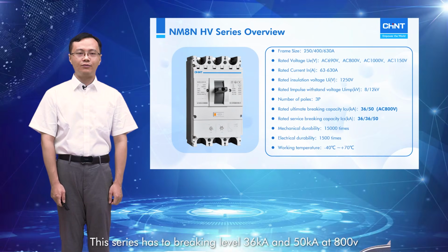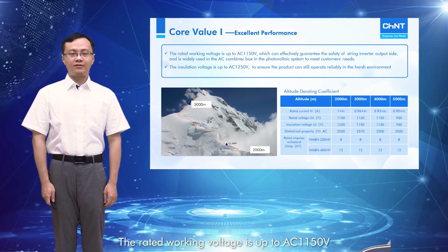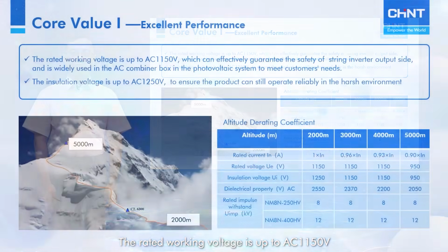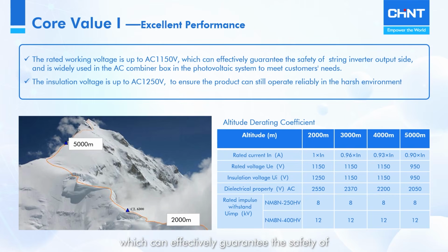This series has two breaking levels, 36 kA and 50 kA at 800 volt. The ICS is equal to 100% of ICU. The rated working voltage is up to AC 1150 volt, which effectively guarantees the safety of the string-type inverter output side, and it is widely used in the AC combiner box in the photovoltaic system to meet customer demands.